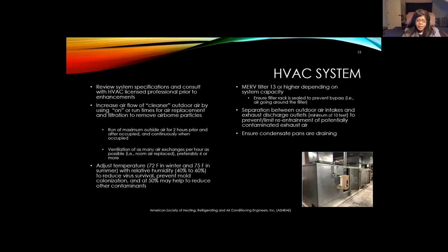We also recommend that the systems be turned on and run continuously or as much as possible to bring in more outdoor air to dilute and remove particles. HVAC systems should run at least 2 hours prior to and after the space is occupied, and continuously when occupied, with as many air exchanges as possible within a space, preferably 6 or more, so that all the air is turned over 6 times or more within an hour.